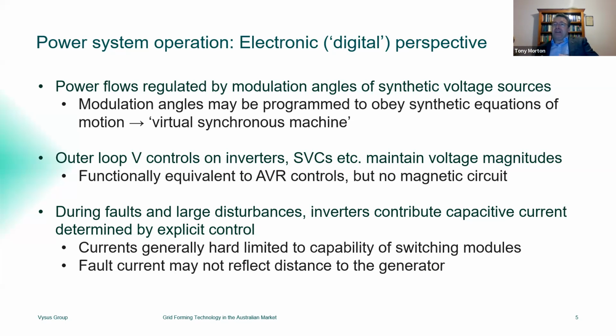Now, they can be programmed in different ways to provide different voltage source characteristics. And of course, the foremost among those at the moment is looking at getting them to operate as a virtual synchronous machine, so that we have a virtual equation of motion that's determining the modulation angle, or the phase angle, of the EMF that the inverter is now presenting to the network. And then, similar to machines, we have outer loop controls that are maintaining voltage magnitudes. Again, very similar to what we do with synchronous machines, except of course that there's no intermediating magnetic circuit.